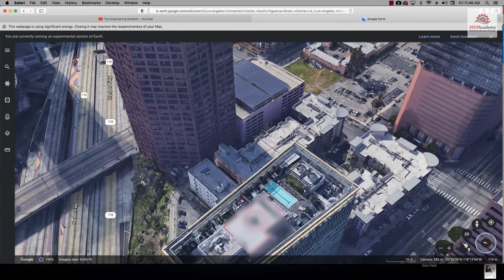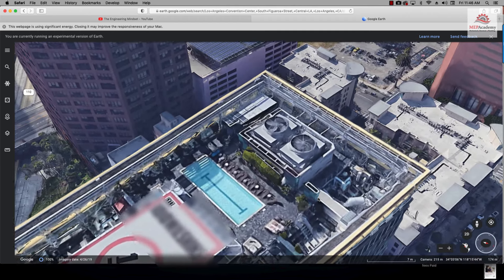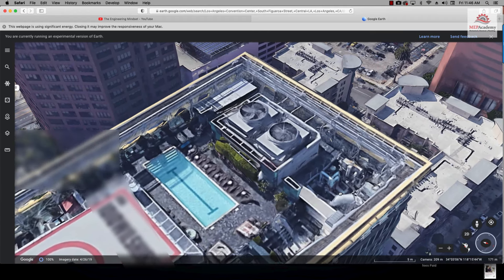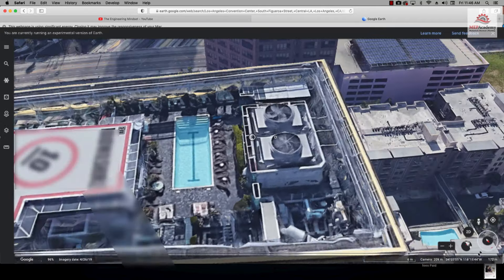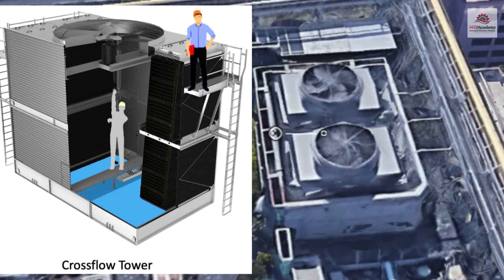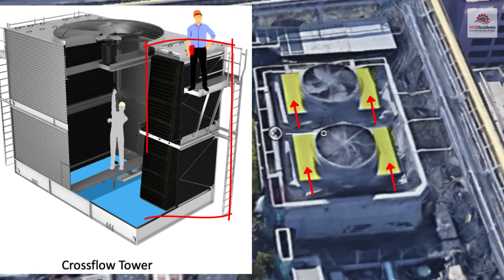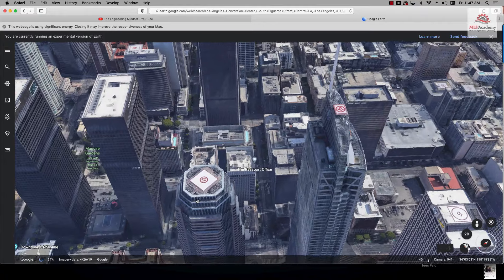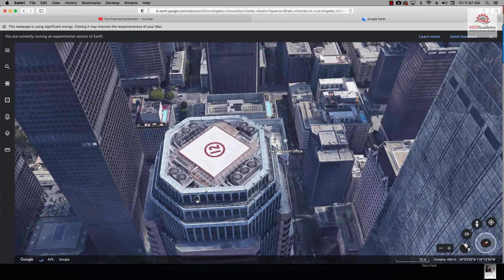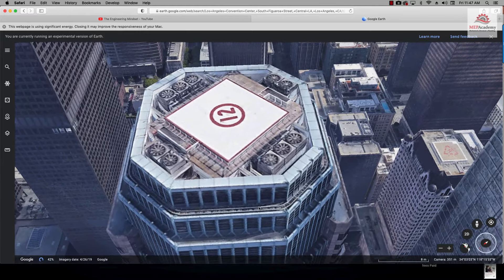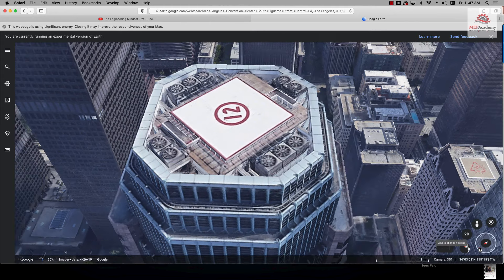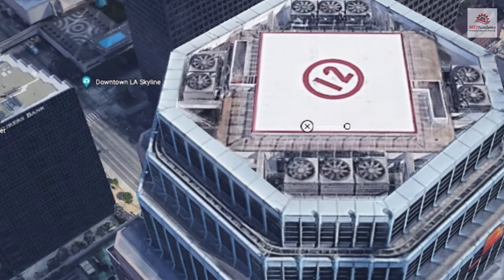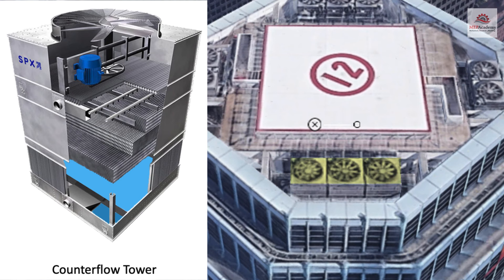Here are the two tower types shown on a typical high-rise building in downtown LA. This first one is a cross flow — you can tell by the large area to the side of the fans, where the fill is located. The fan sits in the middle with fill areas off to the sides. Here's another high-rise with a counter flow: the fan takes up just about the total area of the top of the cooling tower, with fill only directly below since there's no room on the sides. This is how you tell the difference.